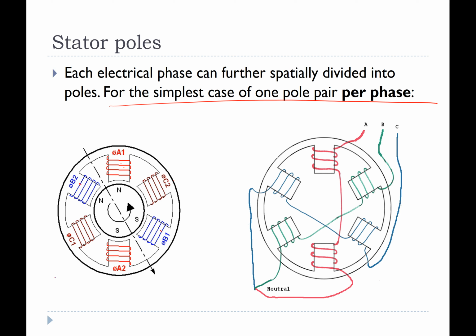And the way this is wound, you'll see, is like a solenoid. So you come in with phase A here, and you're winding it around like this, and it's just like you continue the winding. So imagine if you had a solenoid and you just pulled it apart in the middle and separated the middle, and that is what you would get.